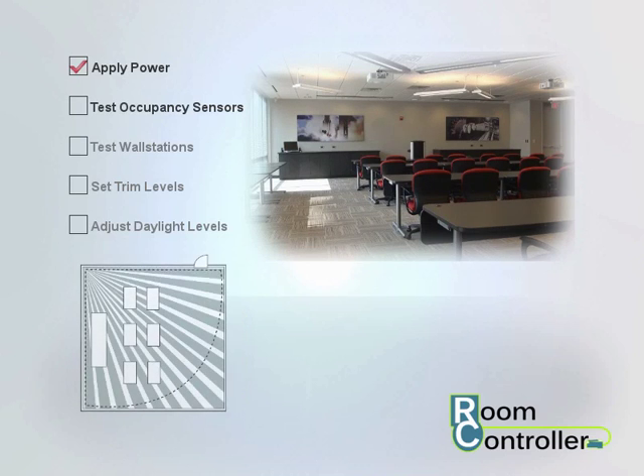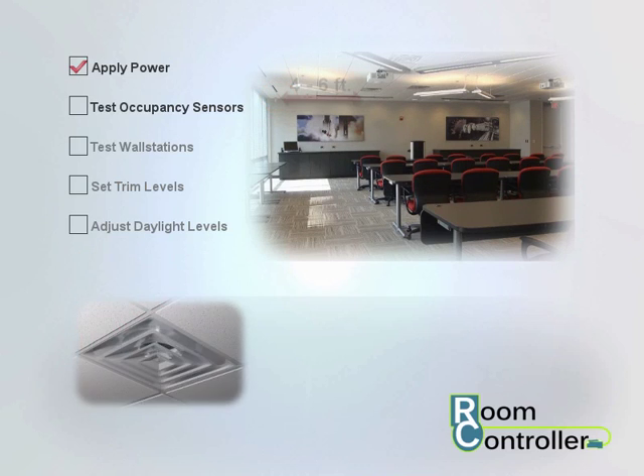For room controllers connected to occupancy sensors, verify that the sensor has been properly located and is at least 4 to 6 feet from any air supply ducts.